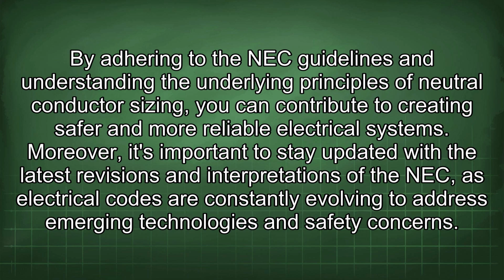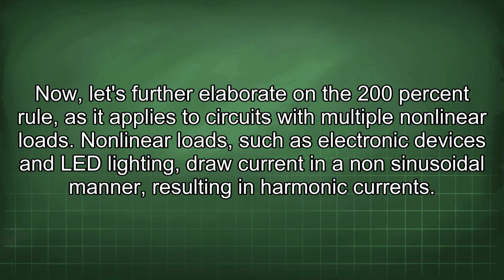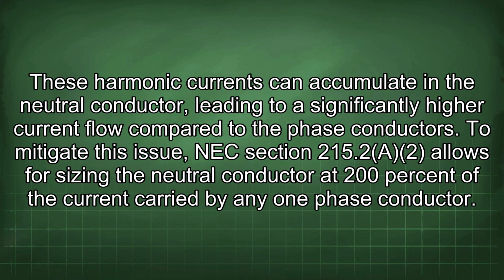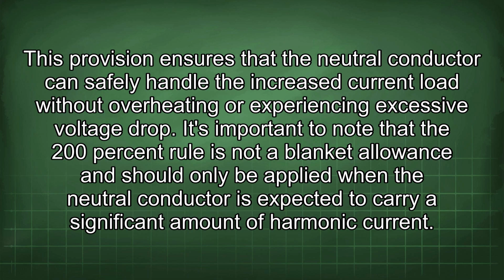Moreover, it's important to stay updated with the latest revisions and interpretations of the NEC, as electrical codes are constantly evolving to address emerging technologies and safety concerns. Now, let's further elaborate on the 200% rule, as it applies to circuits with multiple nonlinear loads. Nonlinear loads, such as electronic devices and LED lighting, draw current in a non-sinusoidal manner, resulting in harmonic currents. These harmonic currents can accumulate in the neutral conductor, leading to a significantly higher current flow compared to the phase conductors. To mitigate this issue, NEC section 215.2(A)(2) allows for sizing the neutral conductor at 200% of the current carried by any one phase conductor. This provision ensures that the neutral conductor can safely handle the increased current load without overheating or experiencing excessive voltage drop.